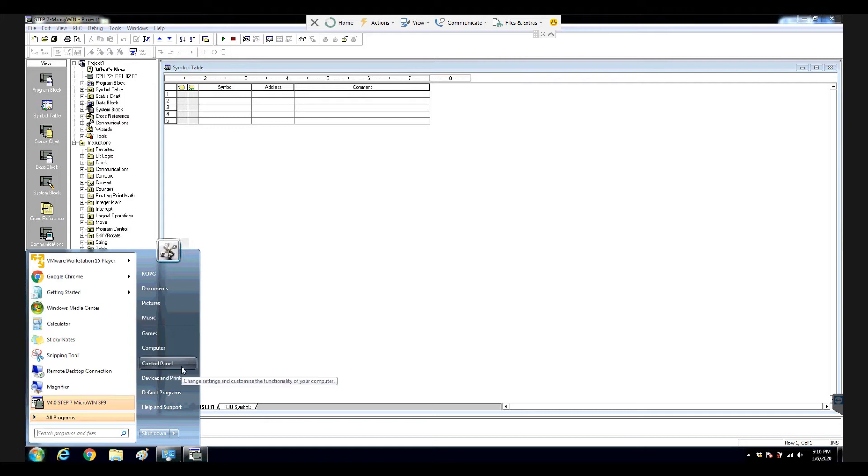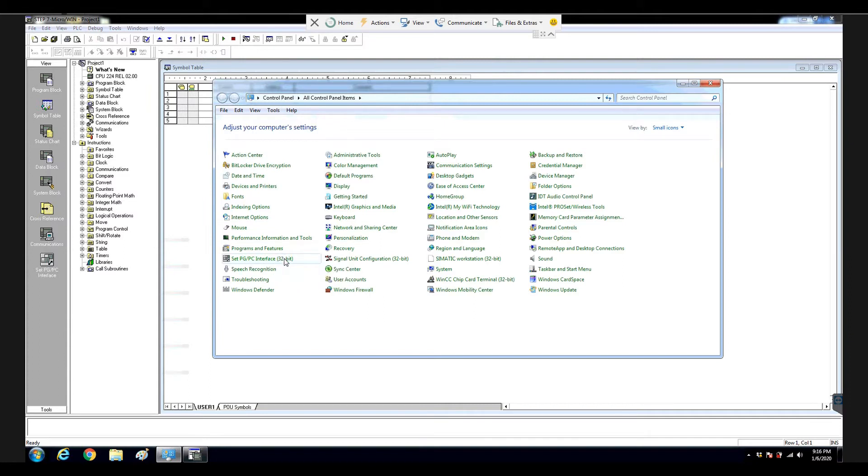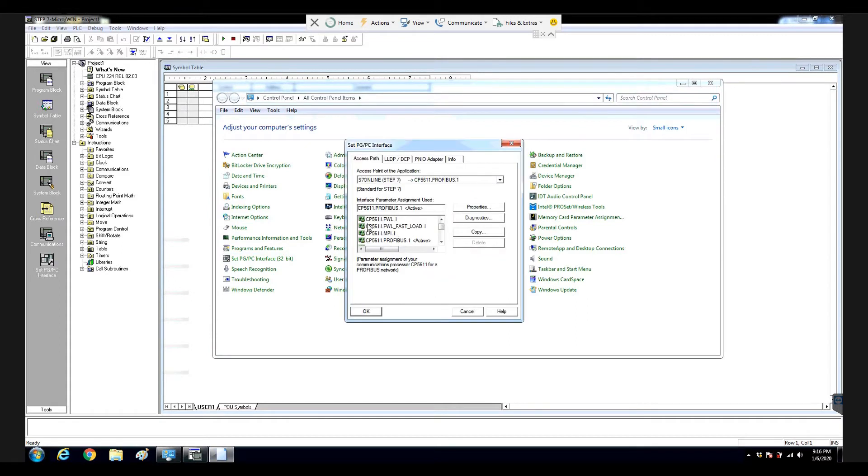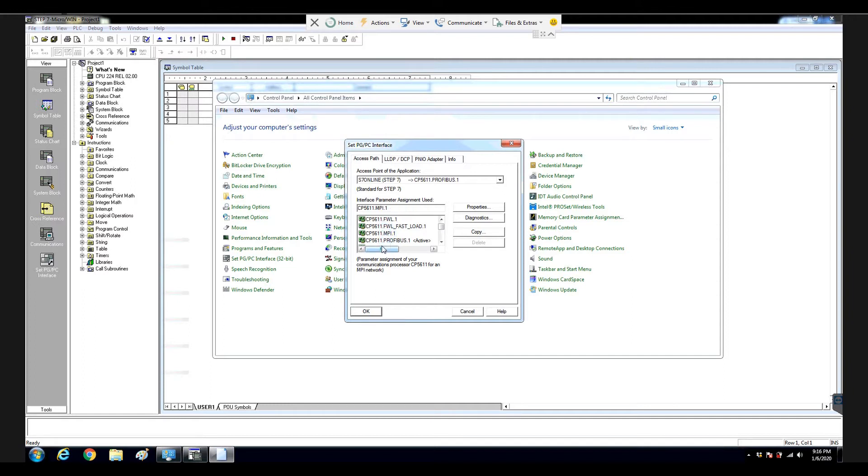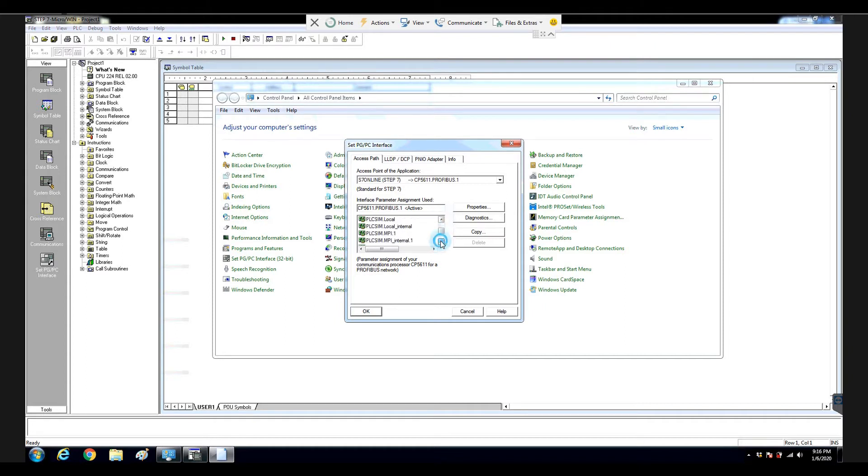So if we go to the control panel, you see set PGPC interface. From here, we can see that this system, the adapter is named CP5611, and this 5611 has a MPI protocol, Profibus protocol. But the thing is that we cannot find CP5611.PPI here. We cannot find it.